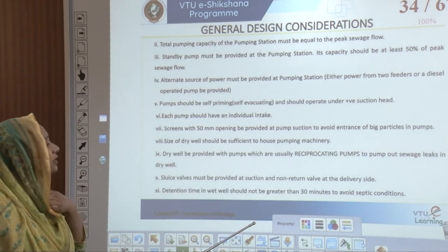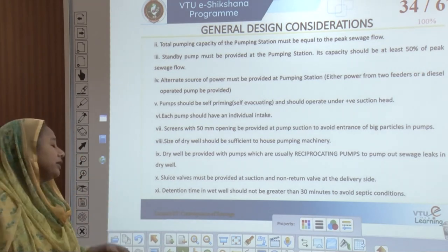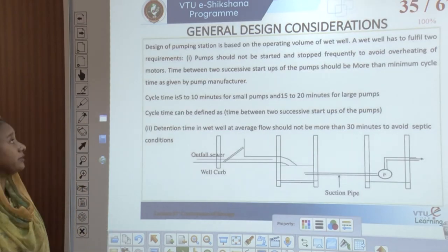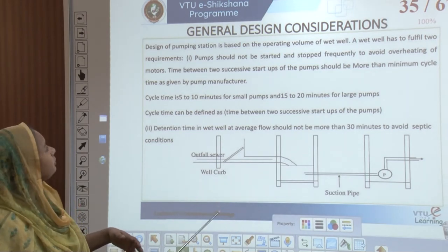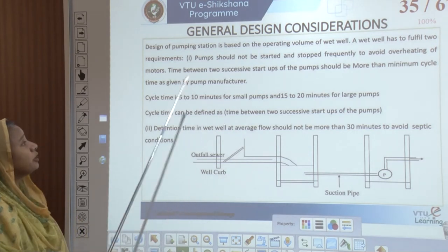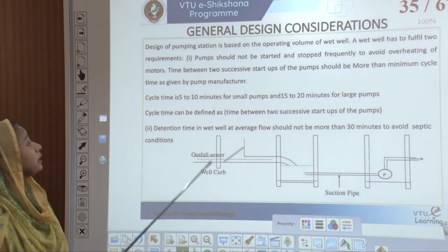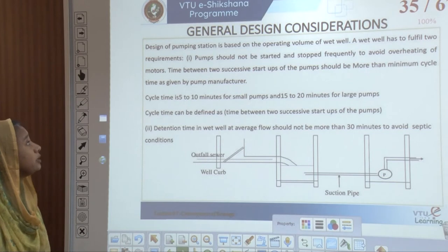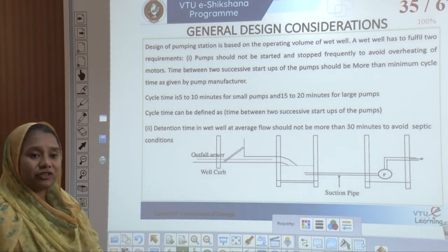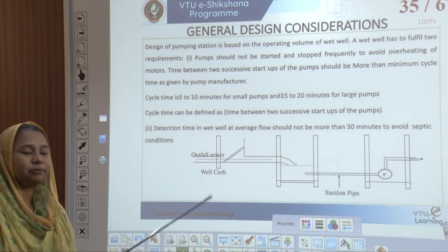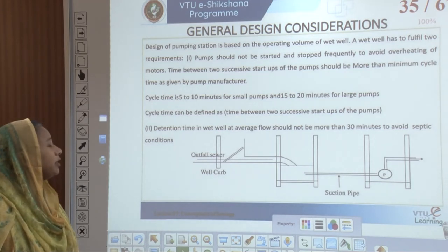Pumps should be self-priming, self-evacuating, and operate under positive suction head. Each pump should have an individual intake. Screens with at least 50 mm opening should be provided at the pump suction. The dry well should be sufficient to house the pumping machinery, and reciprocating pumps should pump out all sewage leaks in the dry well. Sluice valves at suction and non-return valves at delivery should be provided. At the wet well, detention time should not exceed 30 minutes to avoid septic conditions. The cycle time given by the manufacturer is mostly 5 to 10 minutes, and for large pipe pumps at least 15 to 20 minutes.